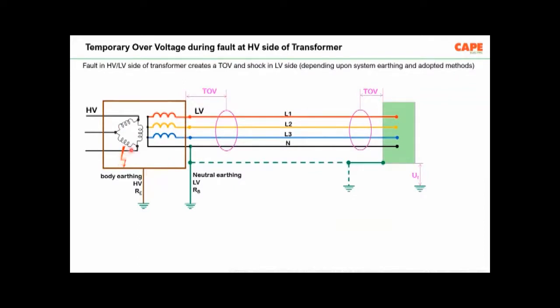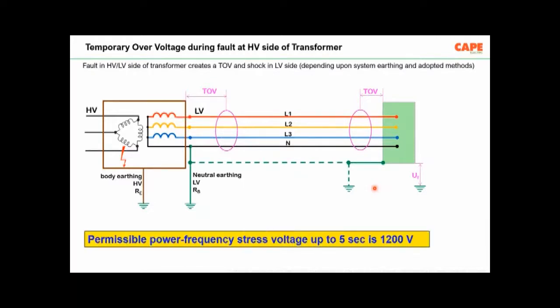Here I am moving the cursor, a fault on the HT side of the transformer. Whenever there is a fault on the HT side of the transformer, there can be problems. TOV at the equipment means the equipment may burn, and people may get a shock. Somebody touching an equipment may get a shock. A good electrical installation must have protection against this problem number 1. That means whenever there is an electrical fault at the high voltage side of the installation, low voltage equipment must withstand it. And the permissible power frequency stress voltage is 1200 volt up to 5 seconds.